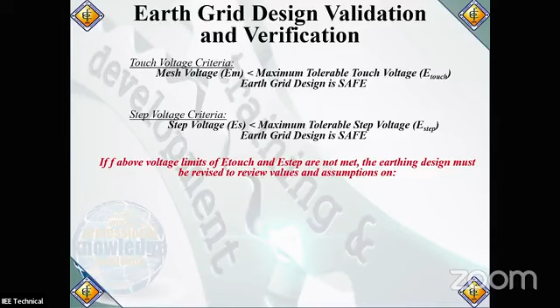Then the second one is step voltage criteria. The step voltage criteria must be less than the maximum tolerable step voltage that is present during the fault. So then, of course, your design is okay. If not, magre-recalculate ka. Mag-iterate ka sa design. And what are these factors that will have to be considered? Ito yun. I'm just summarizing the time duration of fault or the fault clearing time, maximum symmetrical fault value. These are listed in accordance to, tawag ko dyan, yung impact niya, sa importance na niya.